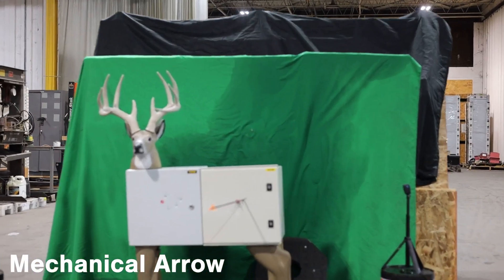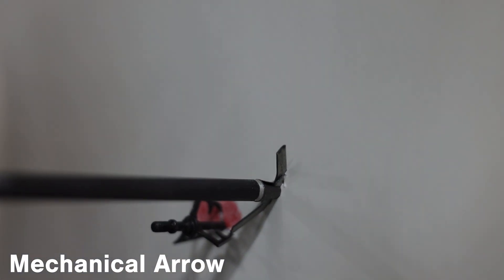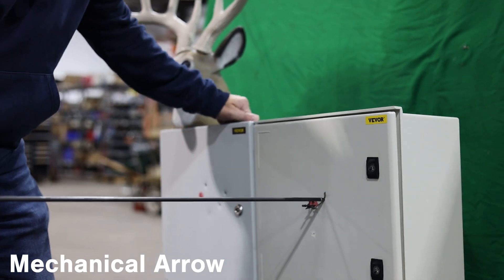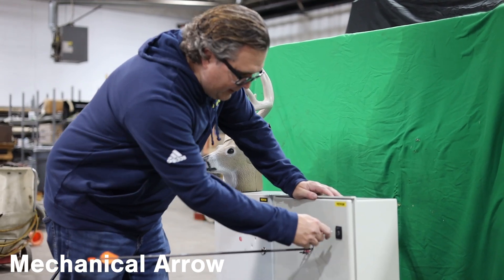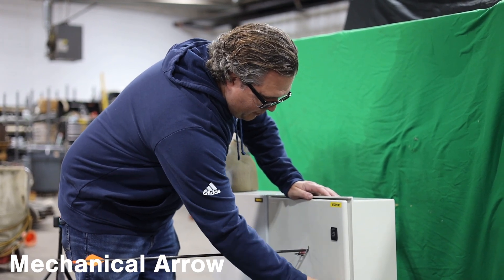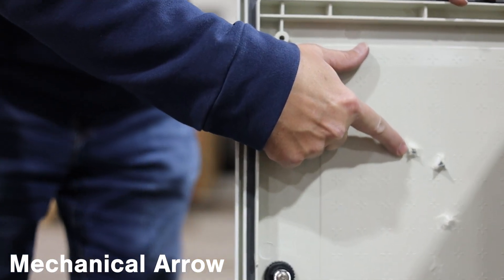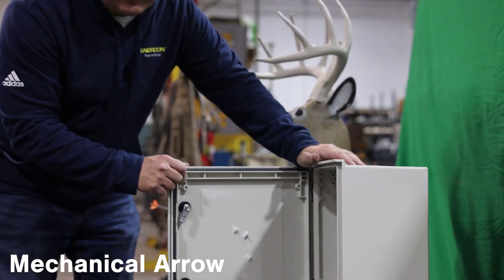Sean was very close to center mass on the fiberglass panel. This one's rated NEMA 3 fiberglass. I'm very surprised — it's holding up almost comparable to a steel enclosure. This did get some penetration with the tip, but not the whole arrow pulling through. As we open this up, it penetrated just a little less than the broadhead that got stuck in there. But seriously, all the components, all the electrical that would be in here — completely safe and secure. There's no way any of that got damaged.